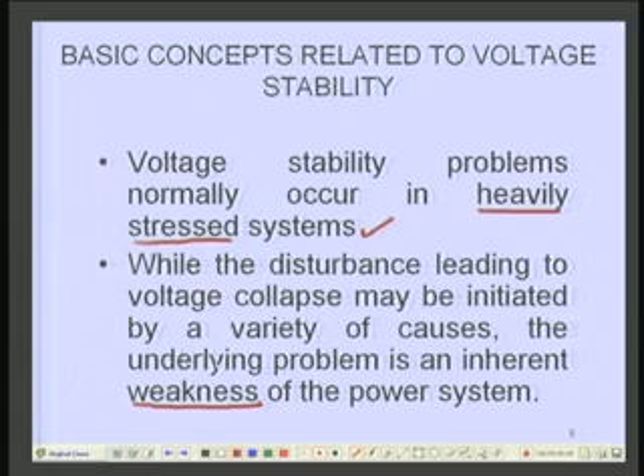Many voltage collapse phenomena have occurred during the last 3 decades, where some sort of disturbance occurs, and you will find that the voltage at most of the buses in the system will go below a certain acceptable level. It is called the voltage collapse phenomenon, and it occurs in a very different type of manner. You trigger some sort of disturbance, voltage drops, and then it continues to drop. We are not in a position to bring it back. If we are in a position to control the system after the disturbance and bring back the voltage to the required level, then it becomes voltage stability, not the voltage instability problem. Therefore, to maintain the system voltage stable, we have to have fast reactive power controls in the system.